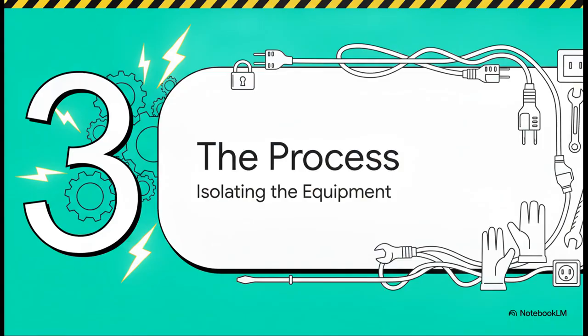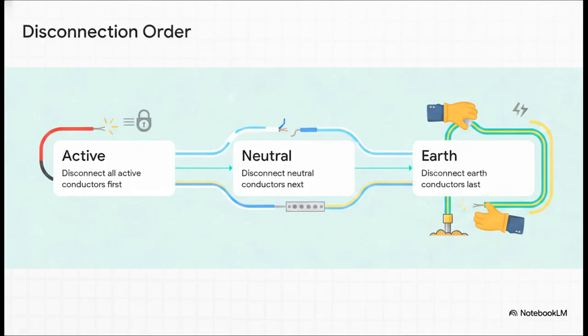Section 3. The isolation process. So the crucial point here is getting the disconnection right. You must isolate the equipment from all sources of supply. And there is an exact, highly recommended, and legally mandated sequence for this. First, you disconnect all active conductors. Next, you disconnect the neutral conductors. Finally, and this is so important, the earth conductors must be disconnected last. Following this specific sequence makes sure your safety systems remain completely intact for as long as possible while you neutralize the threat.